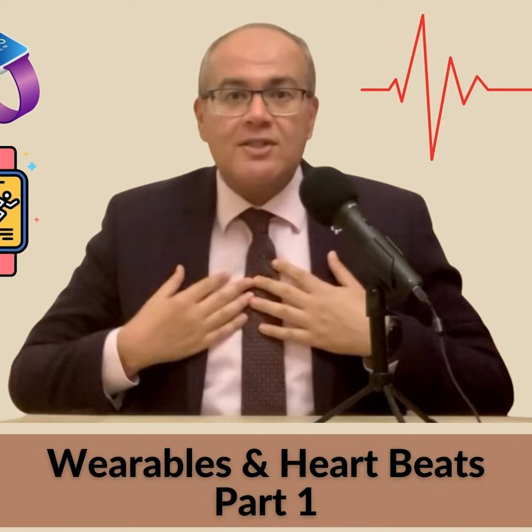Digital devices for heart rhythm monitoring can be divided into two types based on the technology used: ECG and PPG. ECG is the electrocardiogram, where we catch the electricity of the heart from the skin surface. PPG is photoplethysmography. Forget about the long name. PPG depends on light. There is a light source and detector that can be used to measure changes in the blood volume from the surface of the skin. They detect the changes in the reflected light intensity, and they use that change to generate a peripheral pulse waveform.